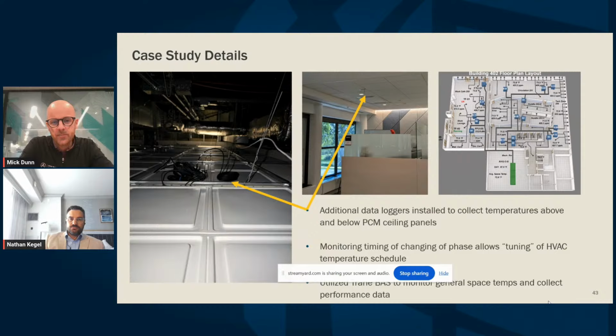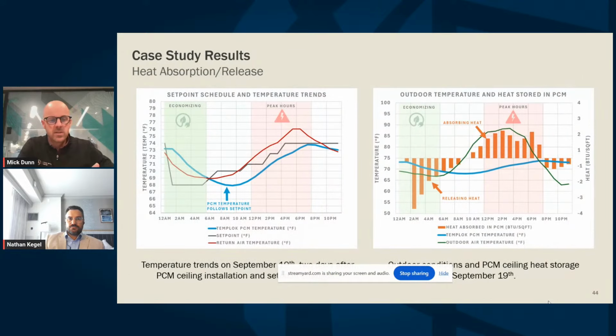We had a series of sensors installed on the tile to measure energy absorption and release, scattered throughout the building, so that we could monitor what was happening and allow us to more finely tune our HVAC operation and test out some of our assumptions. And so the strategy that we employed is on the left. If you look at that black line, that's actually the set point of the space. Like I said earlier, we ran it overnight at 68 degrees and kept that temperature so that we could be really certain that we were beginning the day with a fully charged ceiling.